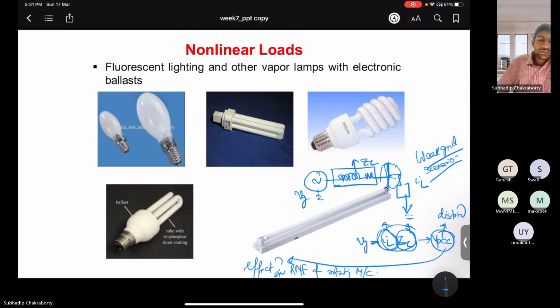Yes. Apart from all the phenomena that are quite prevalent even if the voltages are sinusoidal, what other additional phenomena or disadvantages may happen? This harmonic, because one thing you can understand, whenever we apply harmonically polluted voltages, they have their own harmonic components. So can anyone tell me, if I apply third harmonics? First tell me, can third harmonics exist in a three-phase three-wire system? Can third harmonics flow in three-phase three-wire systems?